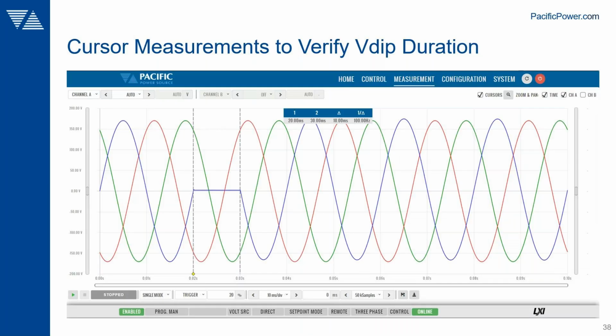At the same time, we can use the scope to measure and verify that it was indeed the right duration. In this case it's somewhat obvious because it looks like a half cycle, but you can use the cursors at the top to position around the event and measure the delta t, which shows you the two times and the delta between them. Sure enough, 10 millisecond half cycle at 50 hertz is what we were looking for. So a simple example.